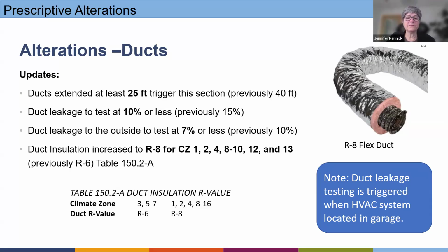the ducts are altered in an existing home that already has a ducted heating and cooling system. There are triggers for when duct leakage testing by HERS raters is required. Under this code, if you extend a duct 25 feet - it used to be 40 - it's triggered, and then the duct leakage needs to be tested to 10% leakage or less, which previously was 15%. Leakage to the outside is now only 7%. And for certain climate zones, the duct insulation has been increased to R8.